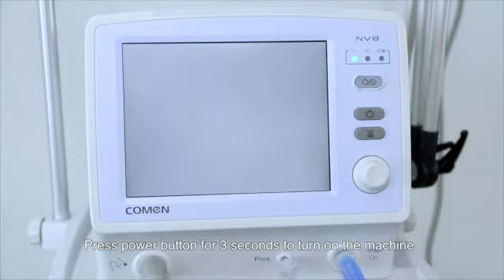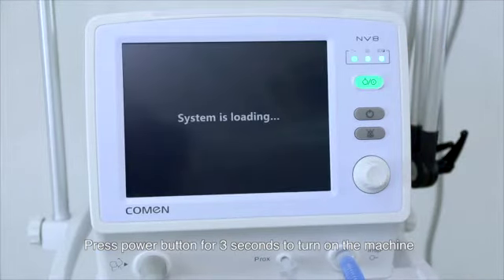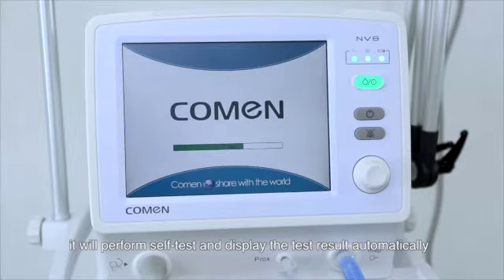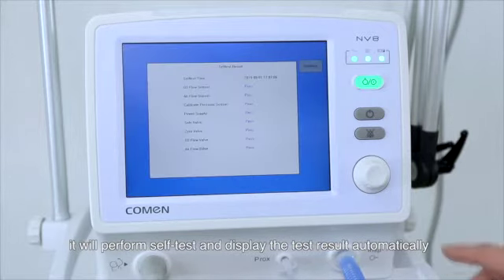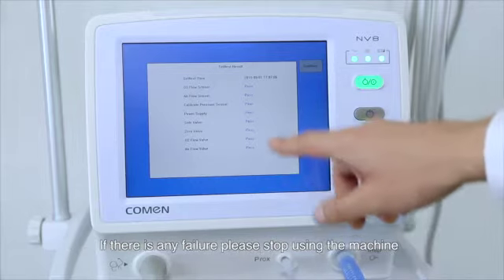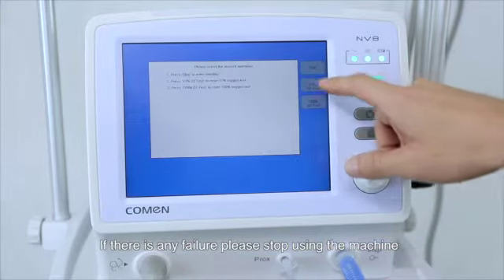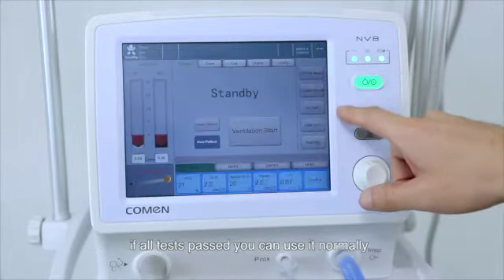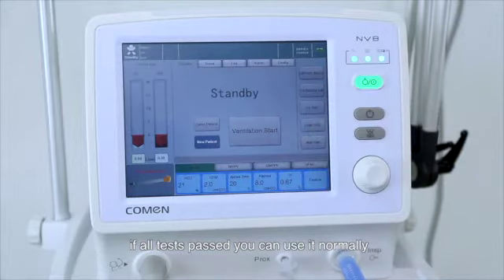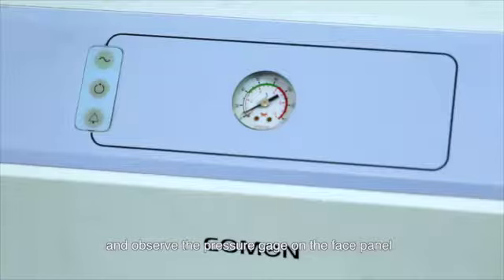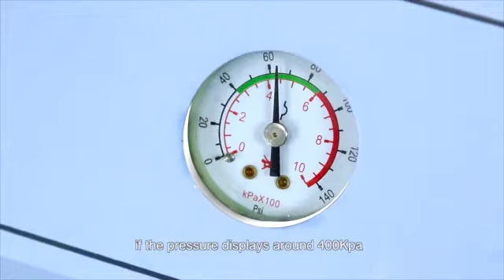Press the power button for 3 seconds to turn on the machine. It will perform a self-test and display the test result automatically. If there is any failure, please stop using the machine. If all tests passed, you can use it normally. Turn on the air compressor and observe the pressure gauge on the face panel. If the pressure displays around 400 kPa within the green zone, then you can use it normally.